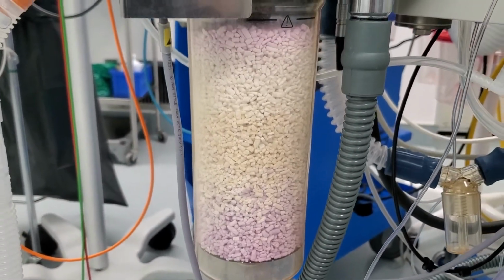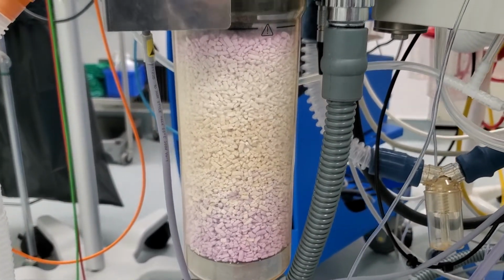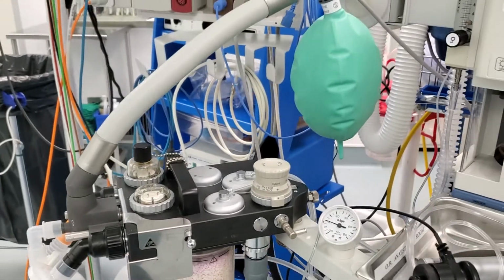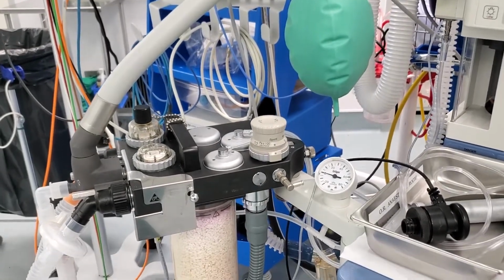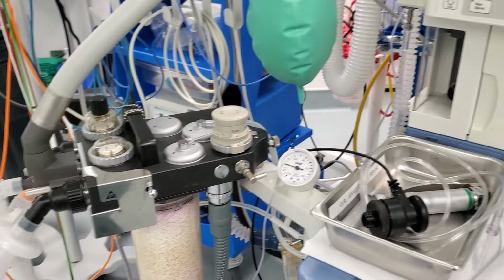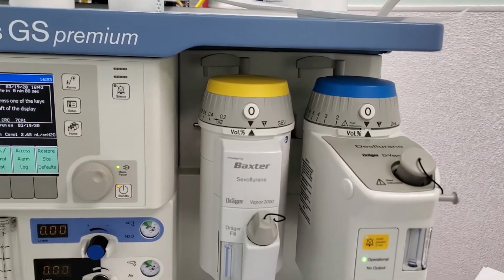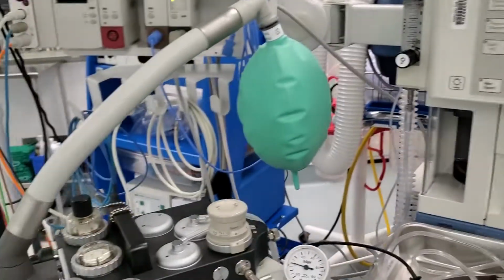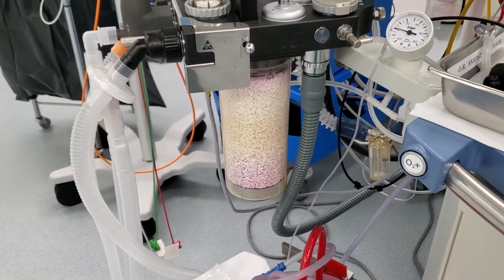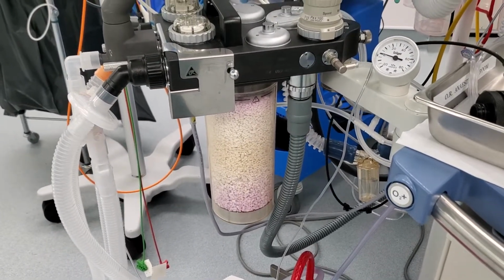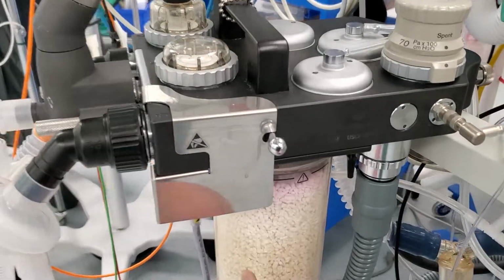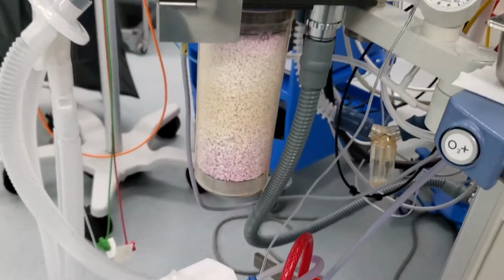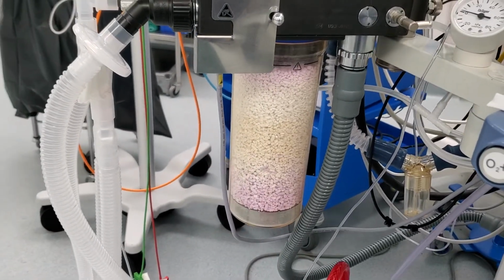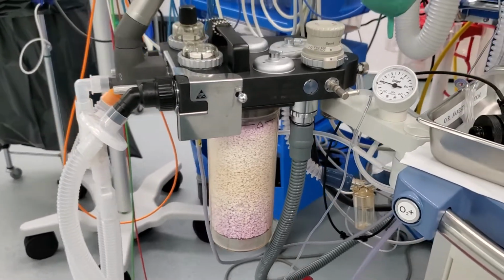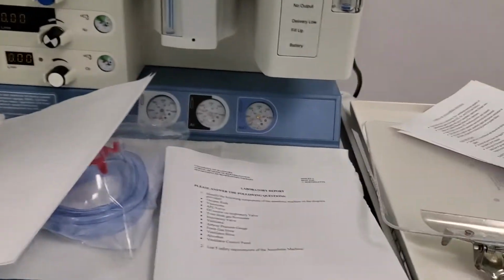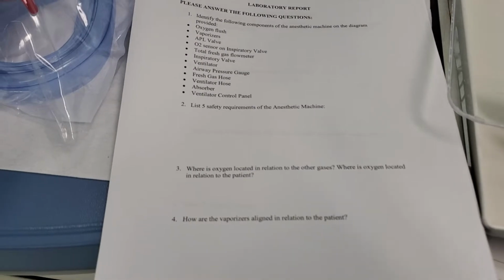So also in the notes you'll learn about CO2 absorbent. Basically, in anesthesia circuits, the gases are rebreathed to help conserve the inhaled agents like the sevoflurane and the desflurane. The only gas that we do not want to rebreathe is carbon dioxide. So we have to take that out of the circuit, and that is done by the CO2 absorbent. The CO2 absorbent that we currently use today is called Litholyme, and you can read about that in the notes as well. Safety requirements of the anesthetic machine.